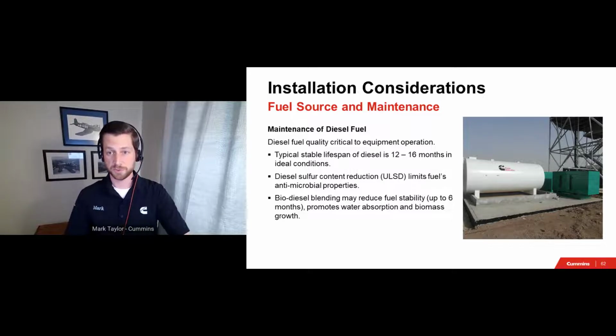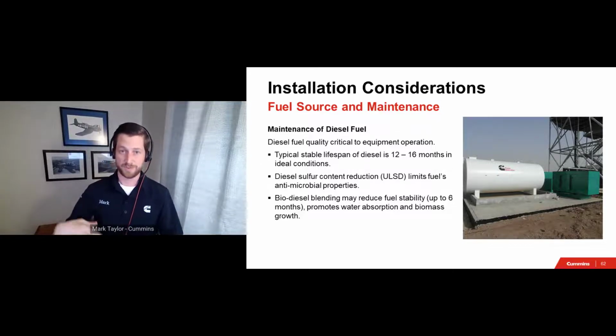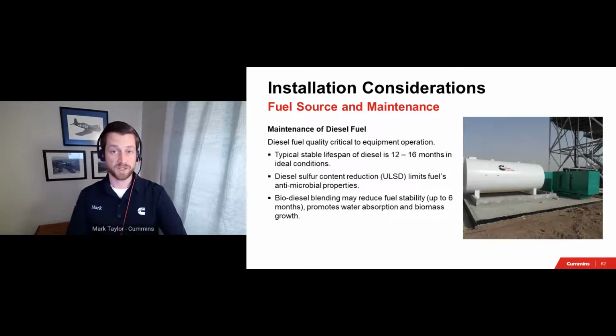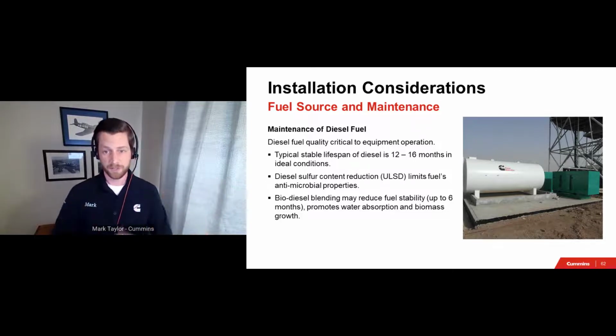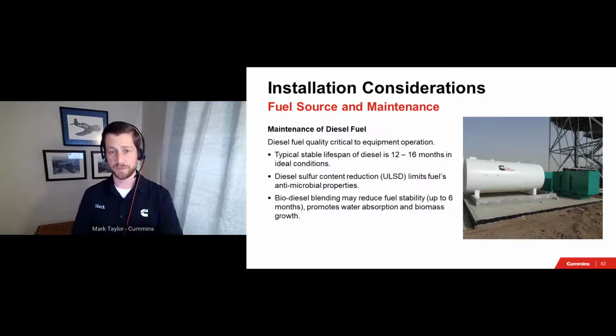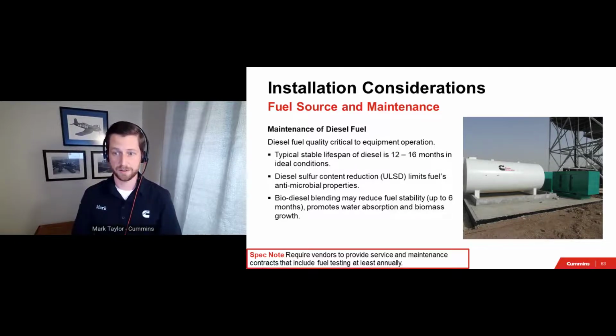to prevent the eventual ingress of water, which could lead to water in fuel and even microbial growth within the fuel. And microbes, when they get sucked in by the fuel pump, they clog up a fuel filter. That could be a down gen set. For standby applications, it is not required, but we do recommend minimizing the amount of biodiesel used to store in on-site fuel tanks. This is not a comment on whether or not engines can handle biodiesel. It's purely coming from a storage standpoint. Biodiesel blends may result in the need for shorter maintenance intervals, as they are more susceptible to spoiling with that water ingress that I mentioned.